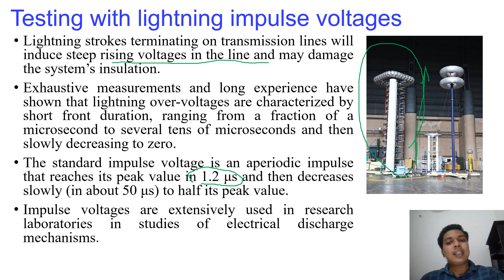Lightning strokes terminating on a transmission line induce steep rising voltages in the line, whose shape I drew in the last slide. Exhaustive measurement and long experience have shown that these lightning overvoltages reach their peak value in 1.2 microseconds, and then decrease to half their peak value in around 50 microseconds. Such a waveform we create inside the lab and apply to our equipment to see what the response is. That is what is meant by testing with lightning impulse voltages.